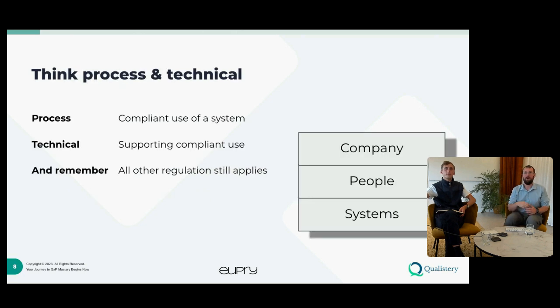Yes, so one thing I would like to point out is often when we get customers asking us regarding 21 CFR Part 11, they'll often think about the technical implementation, so the system. And a very typical question that I get is: is this system 21 CFR Part 11 compliant? And from my perspective, that's actually not possible, because there are no systems in the world that need to adhere to Part 11. Companies have to adhere to Part 11.